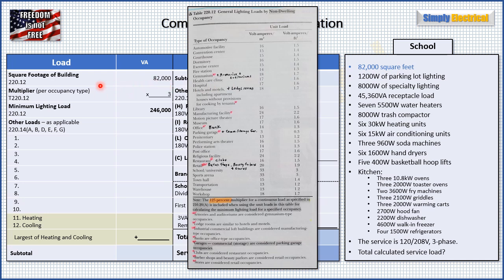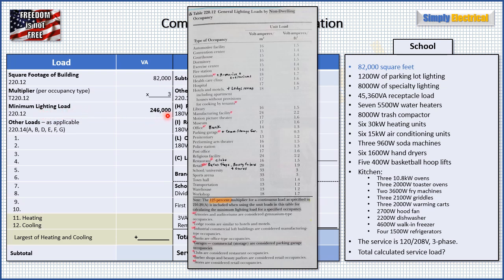In 220.12, our starting point is square footage — we have 82,000 square feet. Next, we find our multiplier from Table 220.12, which lists general lighting loads by non-dwelling occupancy. Heading down to 'school,' it tells us 3 volt-amps per square foot. We multiply 3 by 82,000 and come up with a minimum lighting load of 246,000 VA.